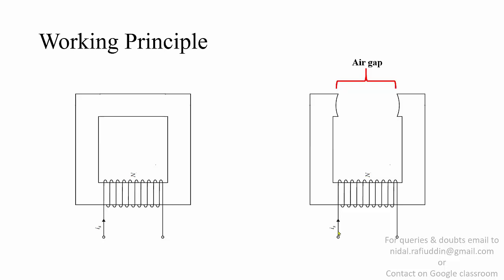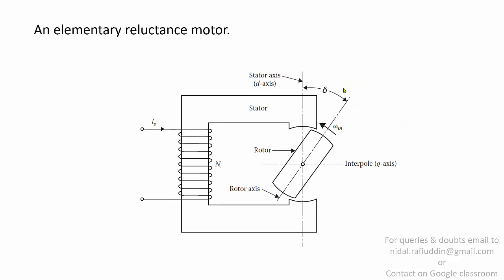To understand the working principle of this motor, let us first understand the property being employed. Shown here are two figures, each having a core made of low-reluctance material — one completely closed while the other has an air gap. Of course the one with the air gap has larger reluctance since air has larger reluctance compared to the core material. This is an elementary reluctance motor comprising a stator core with a winding of N turns to produce a magnetic field, and a small bar as the rotor which is free to rotate. We define two axes: the stator axis or d-axis (direct axis), which goes along the direction of the magnetic field when the stator is energized, and the interpolar or q-axis (quadrature axis), which is perpendicular to the d-axis.